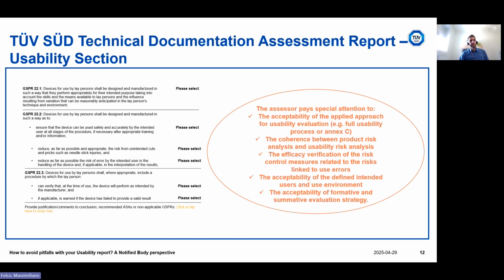What we check is that those parts of risk analysis are coherent. Usually we find the usability risk analysis embedded in the product risk analysis, but sometimes we also have a separate risk analysis, and there should be coherence between the risk evaluation and estimation, and the acceptability criteria that have been implemented and put in place for this analysis.